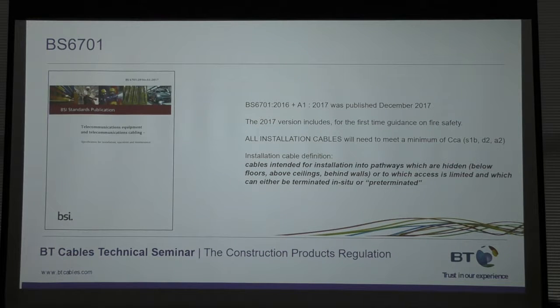Back to BS6701 - it was published in December '17. It had been a code of practice for installation of telecoms equipment previously, but the 2017 version was the first time there was any guidance on fire safety. That decision was taken because of the high density of LAN category cables that go up building risers, through buildings which have a high percentage of polythene in them, which is clearly very flammable.